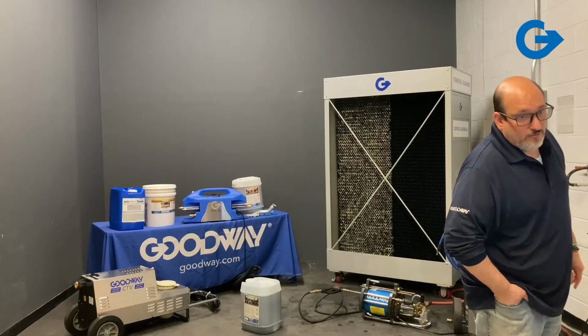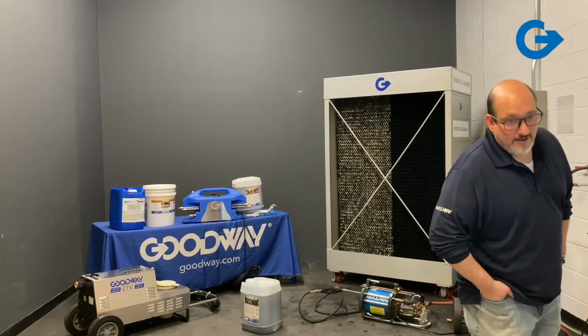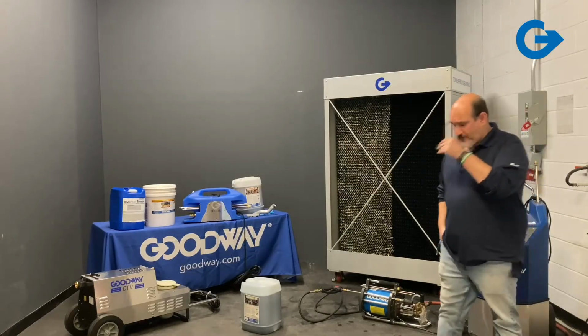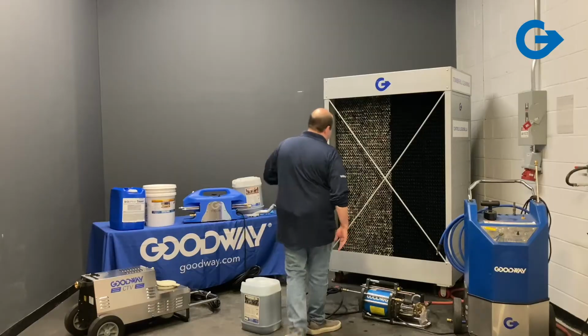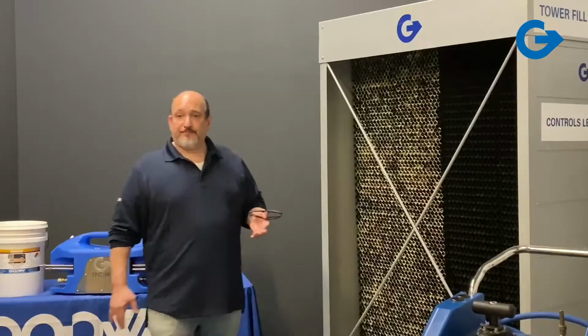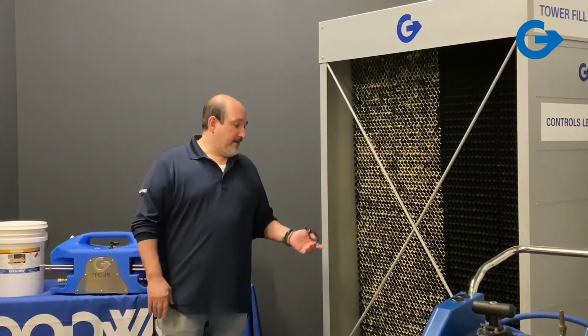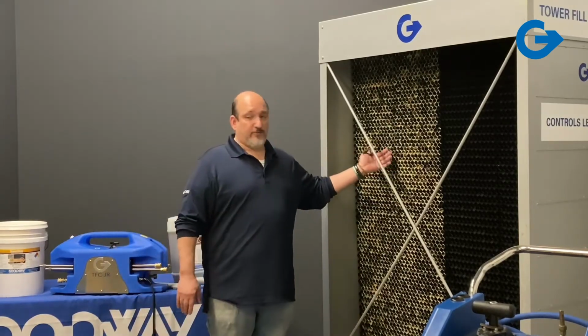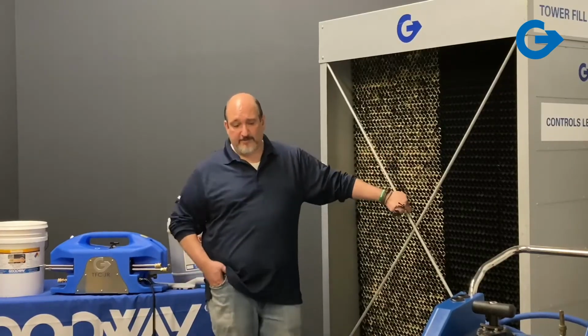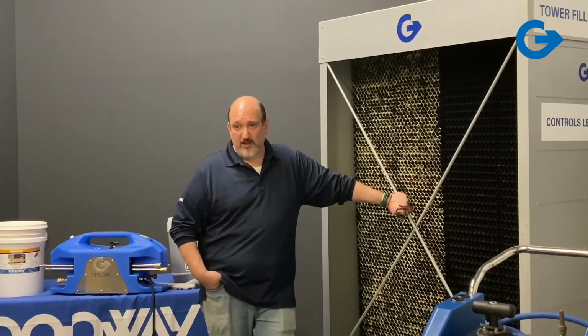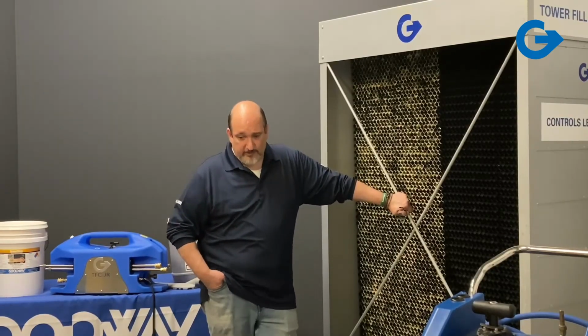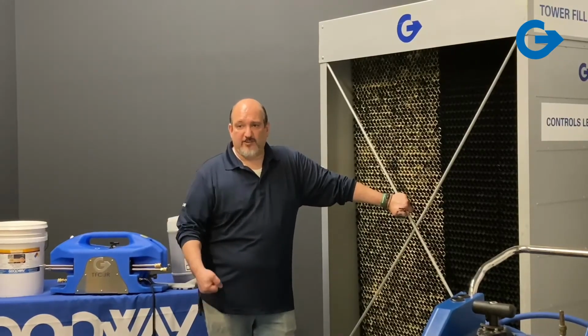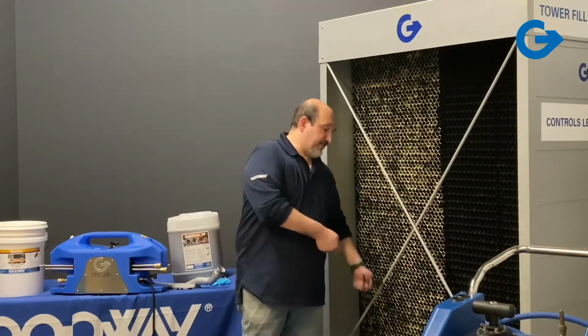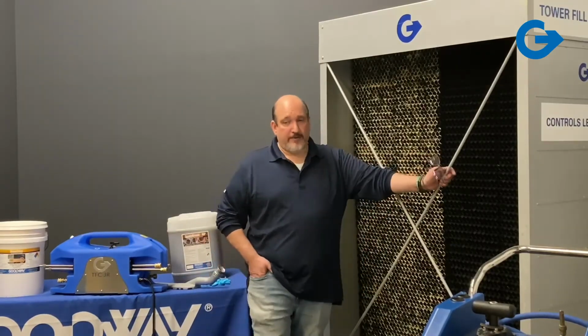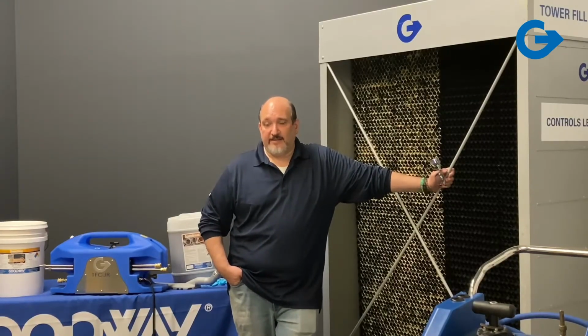Explain what the Scale Break neutralizer is for. We do have a neutralizer too. As you're using gel and cleaning the fill, it has an acidic content, and as it contacts the scale it starts to neutralize itself. But sometimes you don't have enough scale in your system to neutralize all the chemical. So we sell Scale Break Neut, a 25-gallon pail of powdered neutralizer you can use afterward. You add it to the basin and let it circulate for a little bit, and it will neutralize any acidic content still left in your tower—it raises your pH.